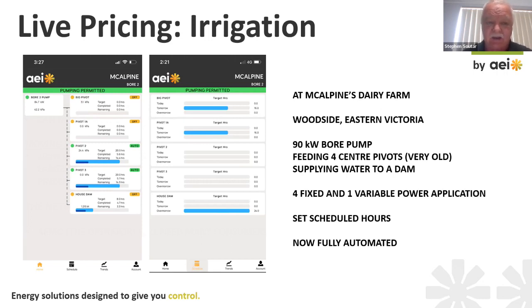This particular system is installed at a dairy farm in Woodside, Eastern Victoria. It has a 90 kilowatt bore pump feeding 4 centre pivots, which were very old, and it supplies water to a dam on another part of the property. It's got 4 fixed and 1 variable power application. You can set the scheduled hours as discussed before, and now the whole system is fully automated, saving significant time for the farmer in operation.